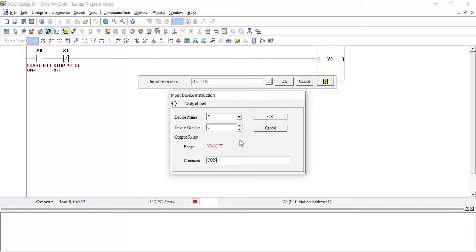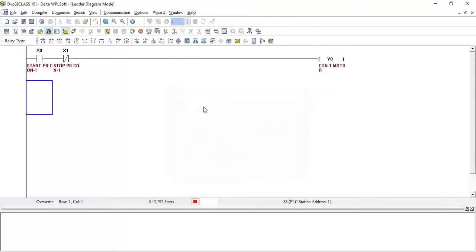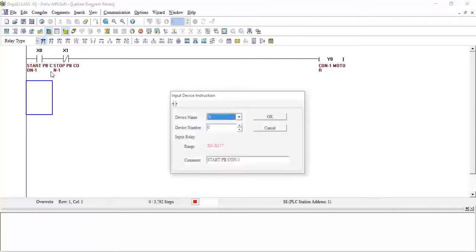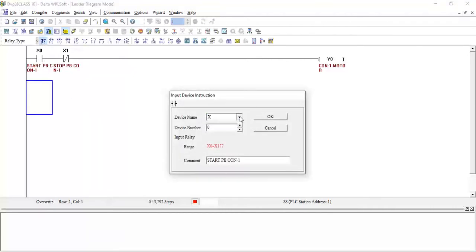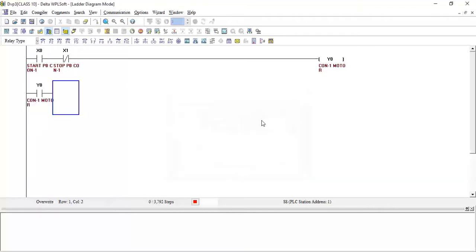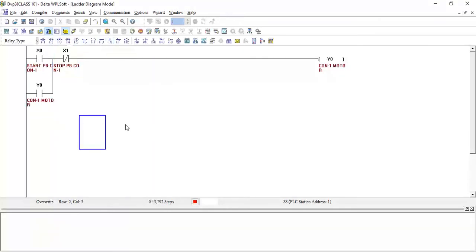Motor conveyor 1 motor, click OK. Also I will add one latching contact. For this I will take Y0 here in parallel, click OK, and I will connect it here. This we already covered in the previous lecture - the latching contact. So this is the ladder logic for the conveyor 1.